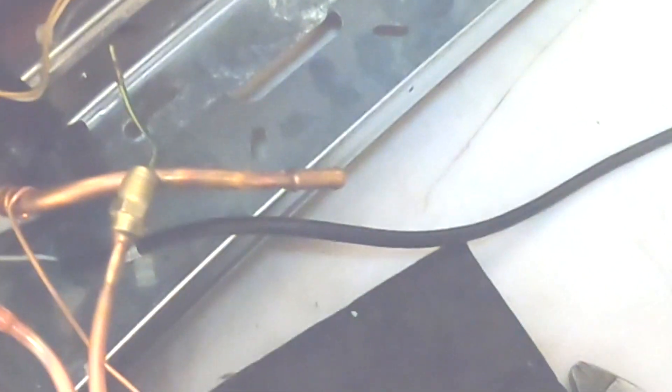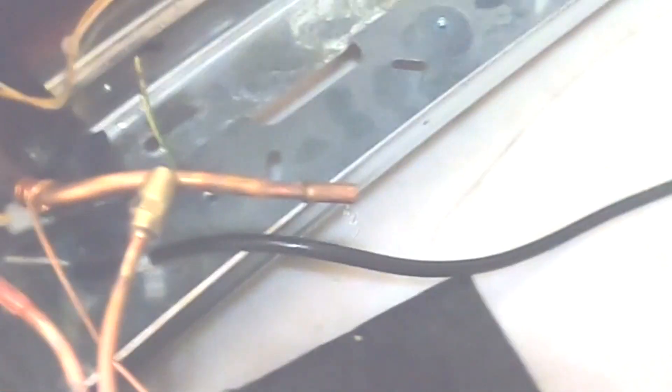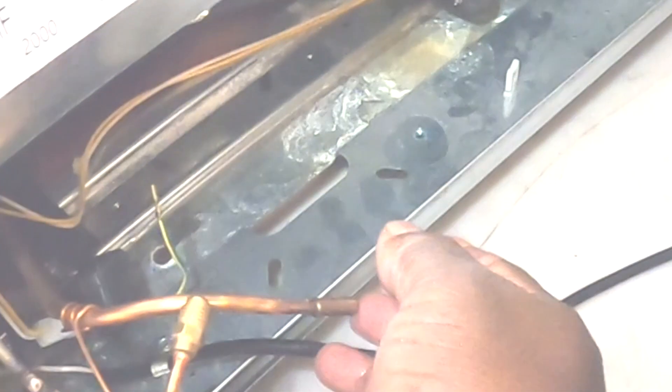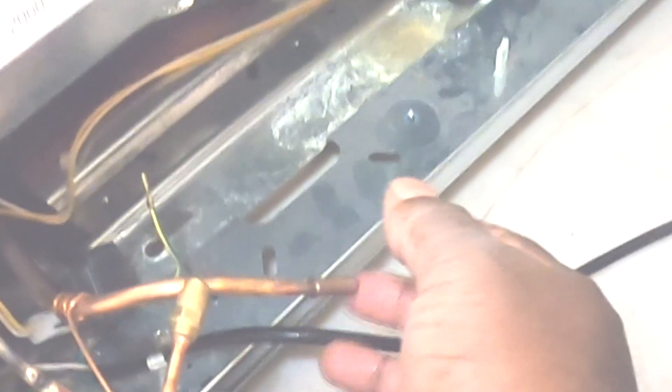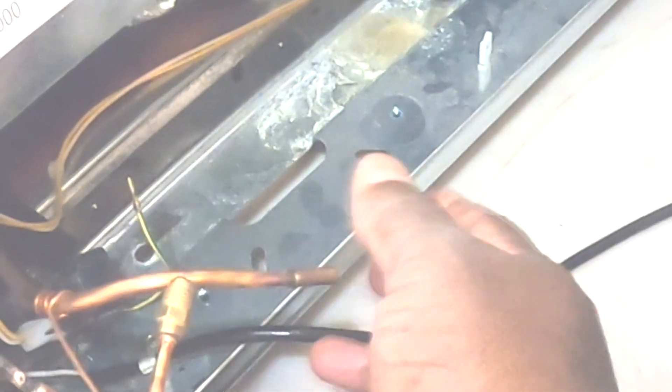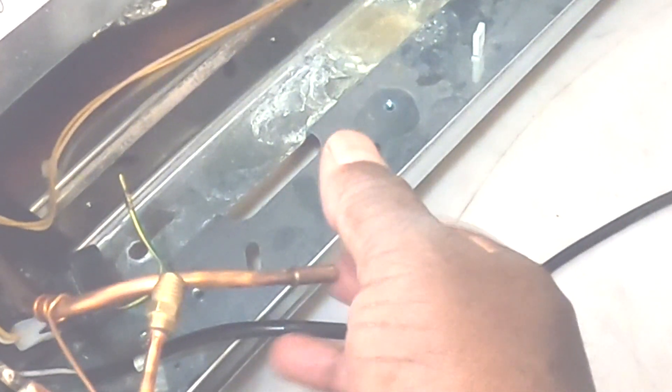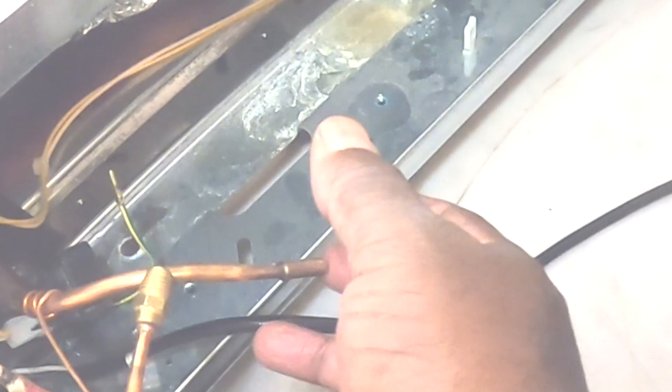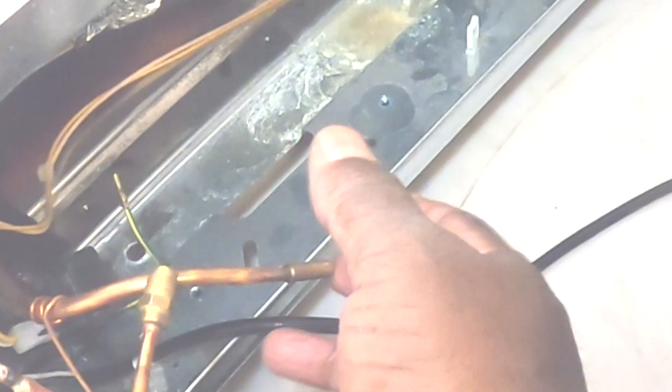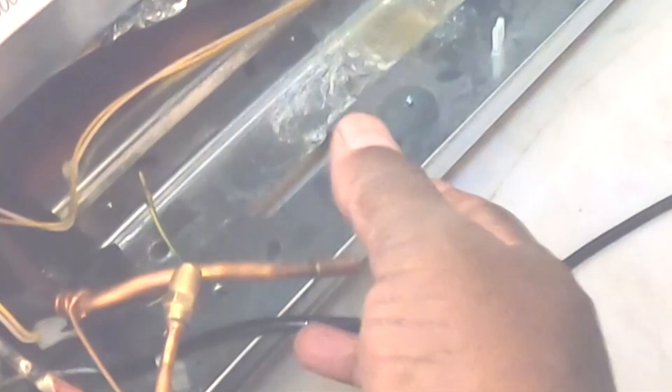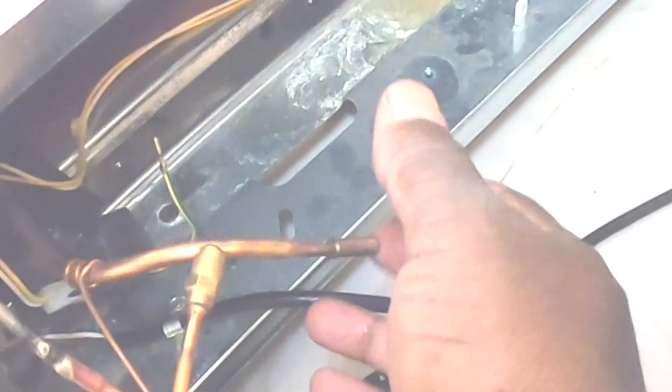I got a leak in the actual evaporator. That compressor has been sucking water through that evaporator and moisture, and got that evaporator filled up with water. That's why it was in a vacuum. What we're going to do is replace the evaporator coil and put a new compressor in here, and we should be good. You see the water dripping out of there?